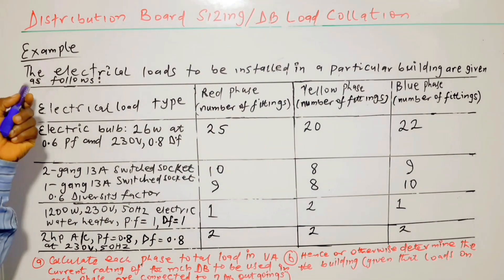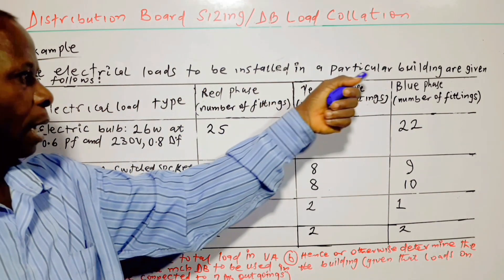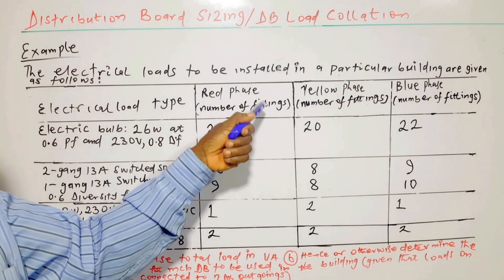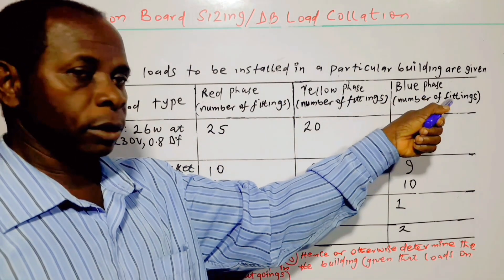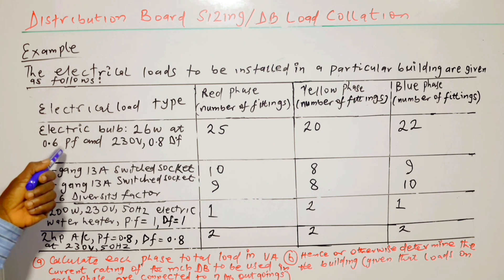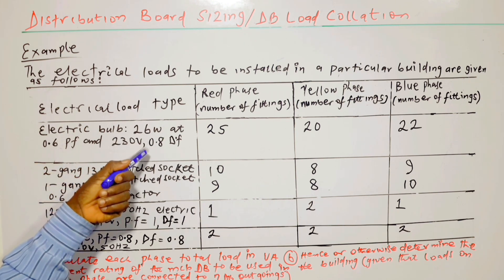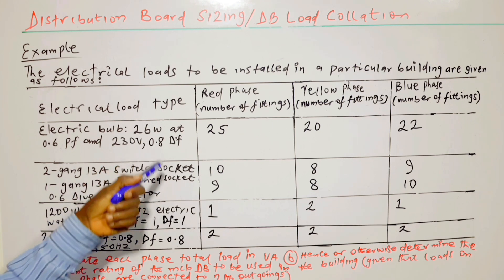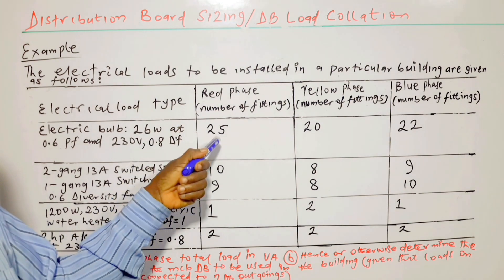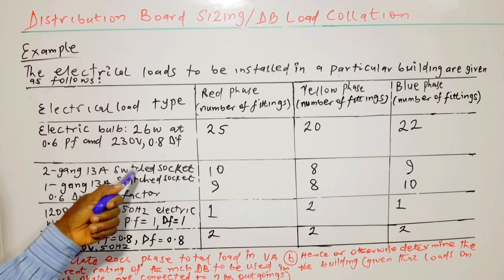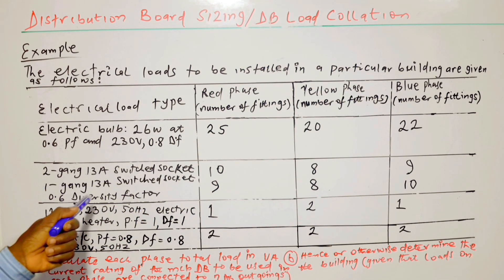The electrical loads to be installed in a particular building are given as follows. Electrical load type — by color: red phase, yellow phase, and blue phase number of fittings or appliances. Electrical bulb: 26 watts at 0.6 power factor, 230 volts, 0.8 diversity factor. We have 25 on red phase, 20 on yellow phase, 22 on blue phase. And 2-gang 13A switched socket at 0.6 diversity factor.